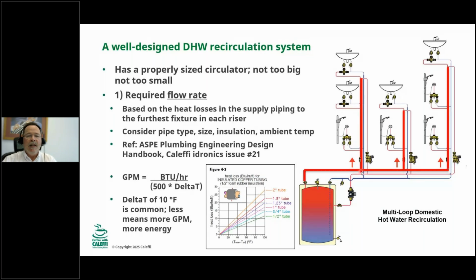So you would calculate the GPM you needed for that section, and you'd do the same for this third section. You would start right here, look at your heat losses for this piece, and come up with a third GPM, and then you add all those together because this trunk has to deliver this GPM, and this GPM. We're not going to get into all the details here because it's all drawn out in Caleffi Idronics issue number 21 if you want to look at the math and the theory behind all that. Just wanted to illustrate that step one is to determine the flow rate for your circulator, and that's the equation you use.